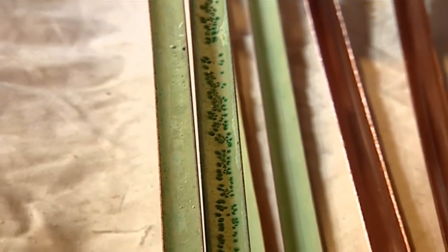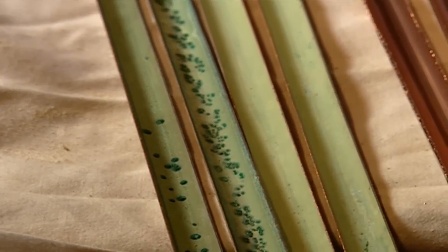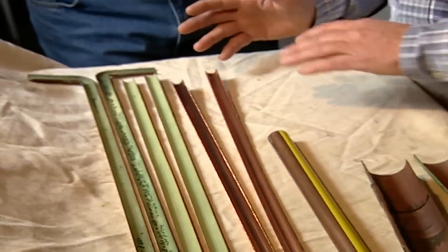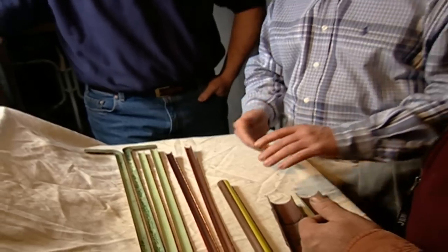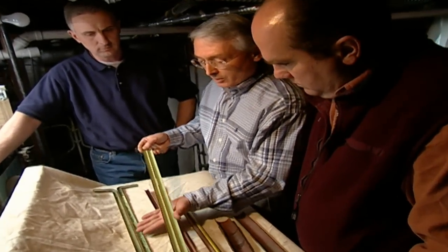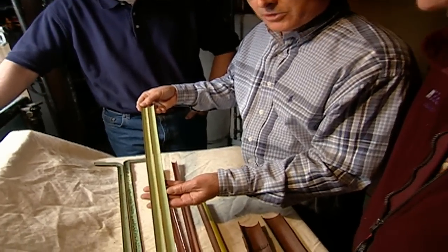That's right. Now, you mentioned something about cold or hot water pipe being more prevalent? Cold water issues are much more prevalent. The reason is that in hot water systems, if you had excessive flux, the heat of the water melts it and carries it away. It would dissolve it, right. This section of pipe is a companion to our cold water sample, and it shows that there are no pits on the inside and the surface is very smooth.